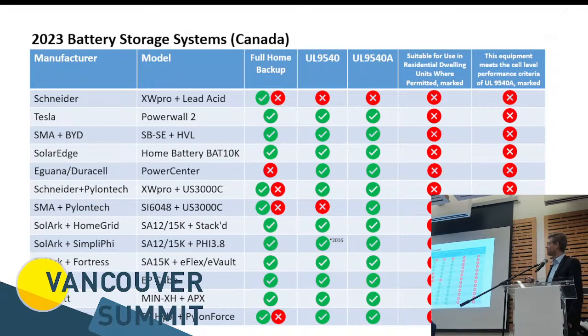Just as a quick run through. Schneider on the 48-volt side, a lead-acid battery can do full home backup, but cannot have the UL 9540 because the standard for lead-acid doesn't exist at the moment. Tesla Powerwall got the certification probably a year and a half ago, so they are fully compliant for full home backup. You have the certification for the system and the fire propagation testing. The SMA system will be fully certified with the BYD battery. SolarEdge with their new BAT10K, not the LG, only their own battery, is UL 9540 and UL 9540A. Eguana out of Calgary, now Duracell, they have the certification.